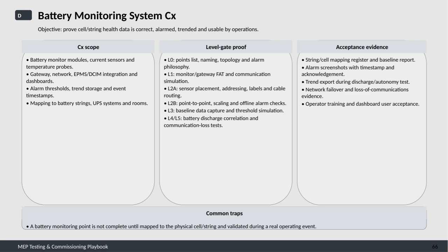A common pitfall in battery monitoring system commissioning is failing to consider a monitoring point complete until it's physically mapped to its actual cell or string and validated during a real operational event. This step ensures the data is truly reflective of the system status and can be trusted for decision-making.